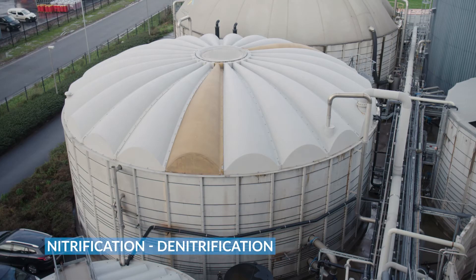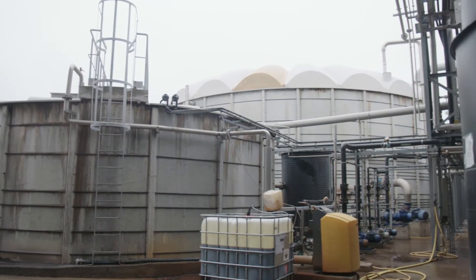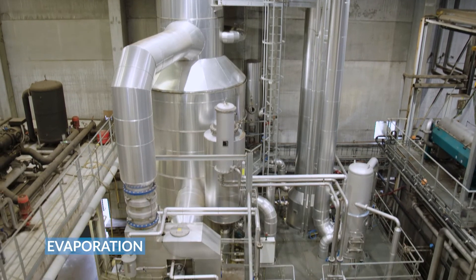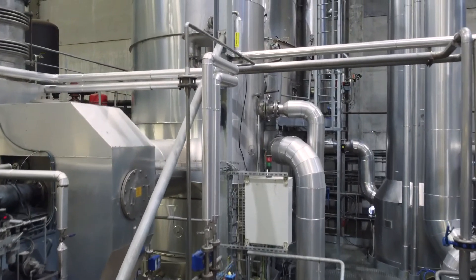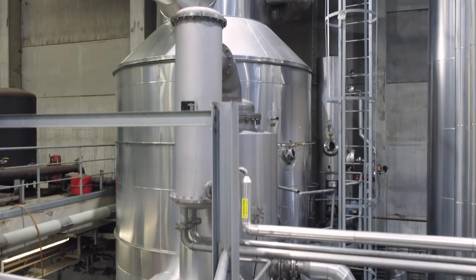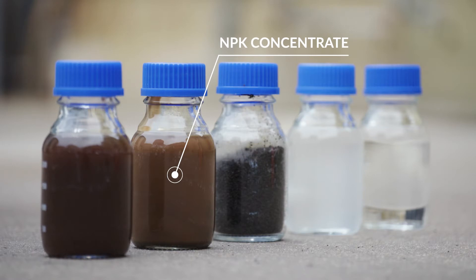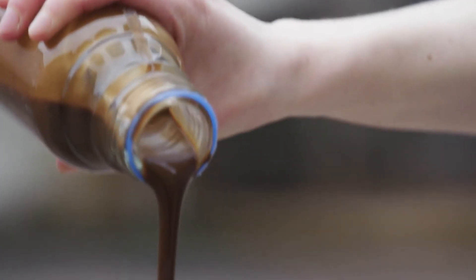The liquid fraction of the digestate is treated in a biological wastewater treatment step, degrading a limited amount of organic compounds. Afterwards, it is sent to a falling film evaporator, which operates at 75 degrees Celsius. As the water evaporates, the liquid fraction is thickened up to a dry matter content of 20%. The resulting concentrate is mixed with the dried solid fraction or exported as organic fertilizer.